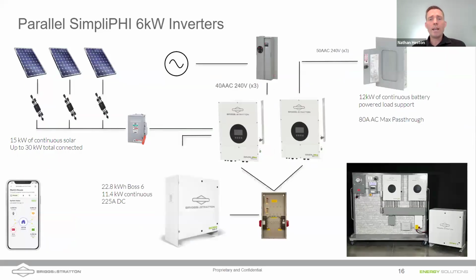So when we're looking at backing up the entire loads panel of a house or large amounts of those loads, we have to consider sizing our inverters and batteries to be big enough to do this. One way to be able to power more of your loads is, of course, to parallel multiple inverters. The Briggs & Stratton inverter that you see on your screen, we can parallel up to 4 of those. 2 of those will give you 12 kilowatts of output power. But the downside to this configuration is that we only have 40 amps of pass-through per inverter.